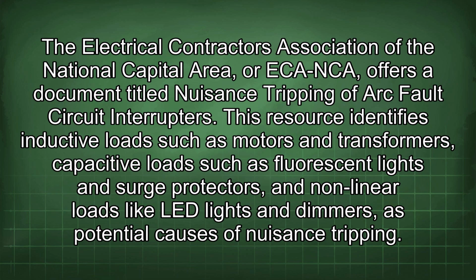The Electrical Contractors Association of the National Capital Area, or ECA-NCA, offers a document titled Nuisance Tripping of Arc Fault Circuit Interrupters. This resource identifies inductive loads such as motors and transformers, capacitive loads such as fluorescent lights and surge protectors, and nonlinear loads like LED lights and dimmers as potential causes of nuisance tripping.